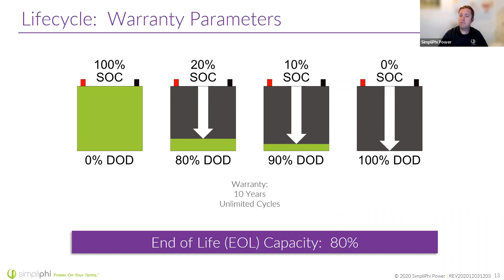When it comes to temperatures, any lithium-ion chemistry really doesn't want to be charged below freezing. So for charging temperatures, our window is 32 degrees Fahrenheit to 120 degrees Fahrenheit. The operating temperature, which is discharge or at idle, is -4 to 140. Now, if you're in a situation where you're going to be colder than 32 degrees Fahrenheit and you're going to be wanting to charge these batteries, there are other ways to do that. And we have other trainings where we talk about how we can mitigate these cold temperatures.